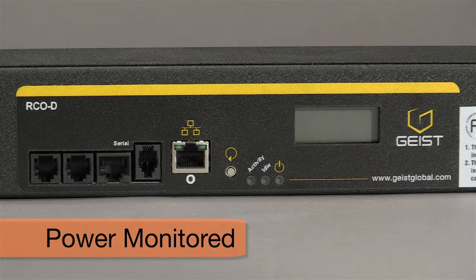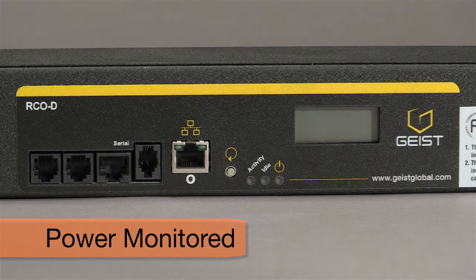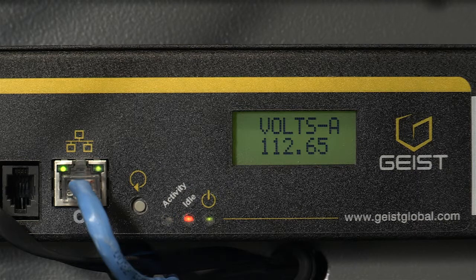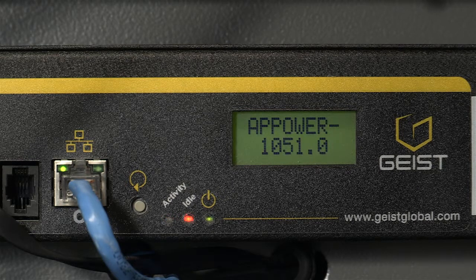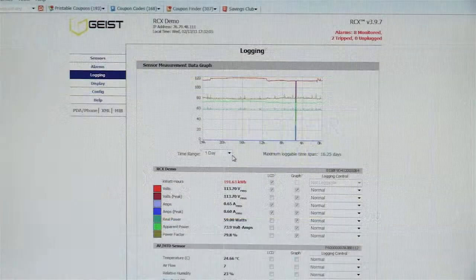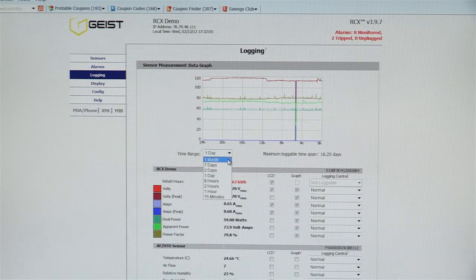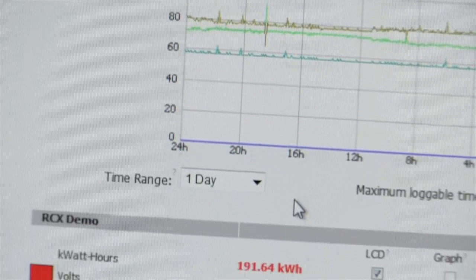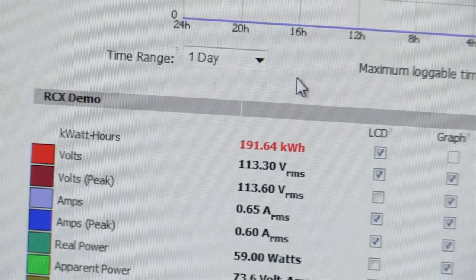Power Monitored PDUs feature external sensor ports, giving the IT manager the ability to track critical climate variables. These units also track more power data, including current, volts, real power, apparent power, power factor, and kilowatt hours. These PDUs provide data logs so that changes can be detected before they become critical, giving the IT manager time to prevent a potential system failure.